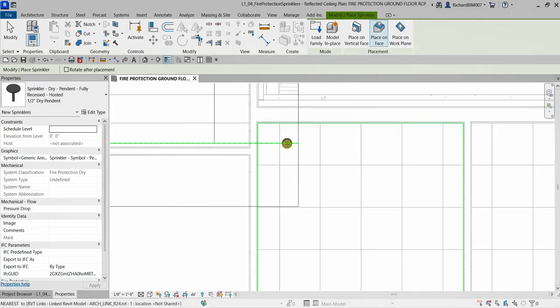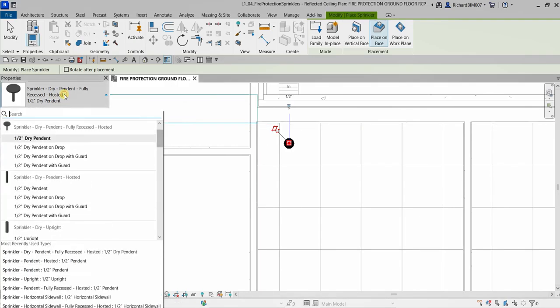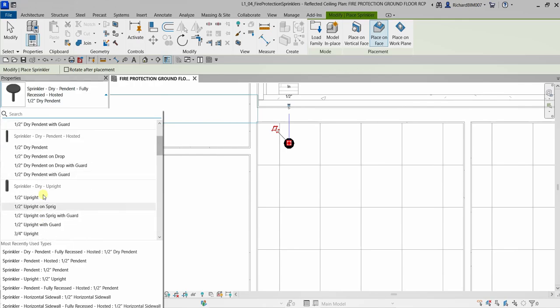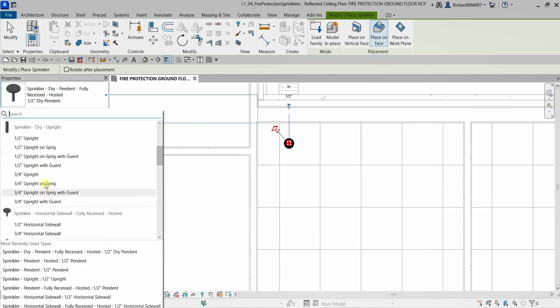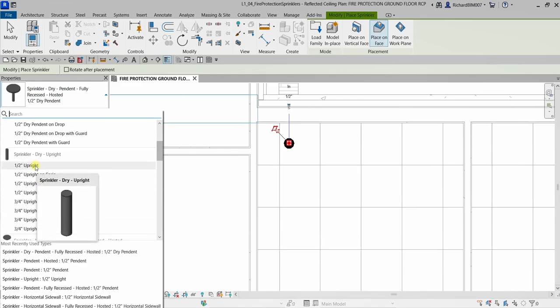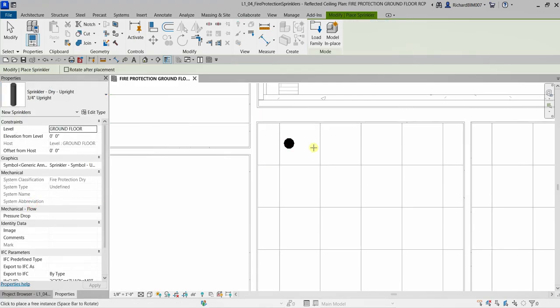Click to place the hosted sprinkler. Now let's switch to a non-hosted family — Sprinkler Dry Upright, one-half or three-quarter inch. This is a non-hosted family, so those placement face options are not available. You need to manually specify the elevation offset.